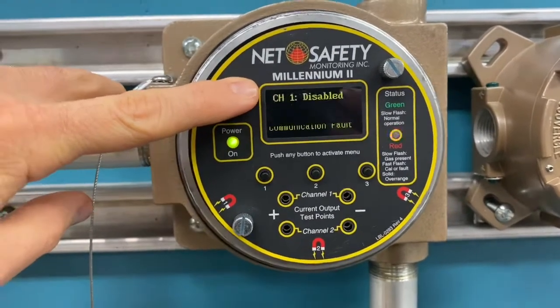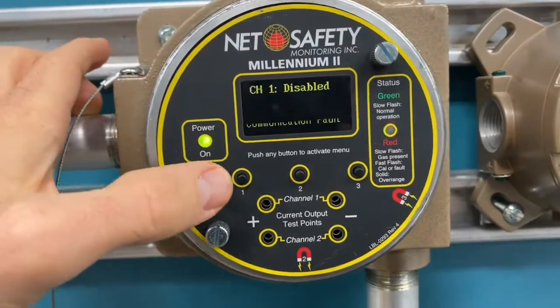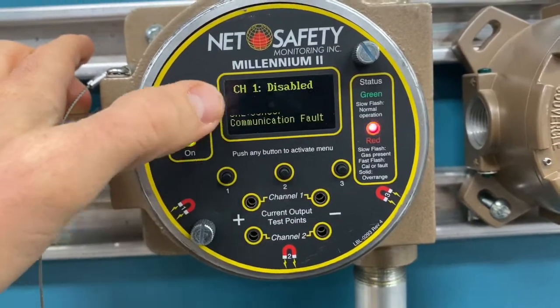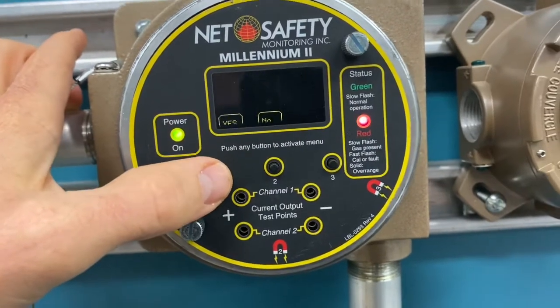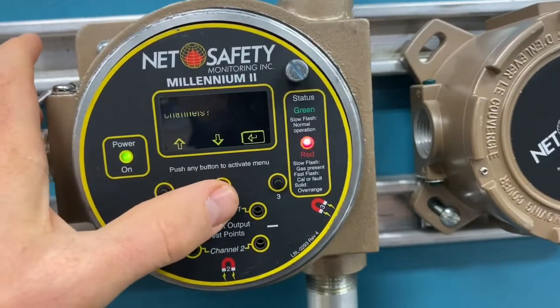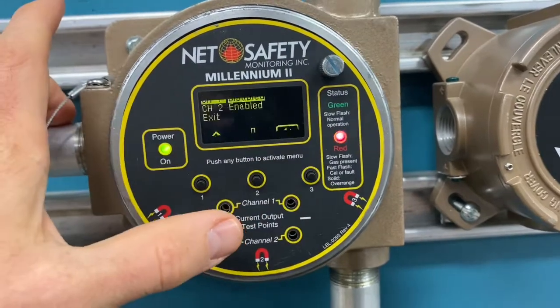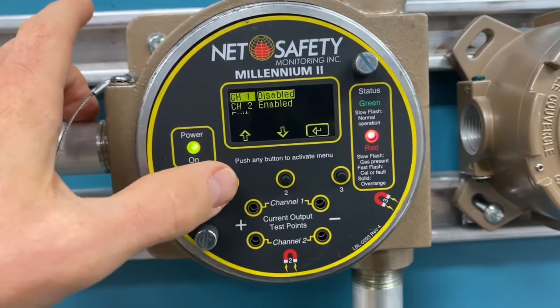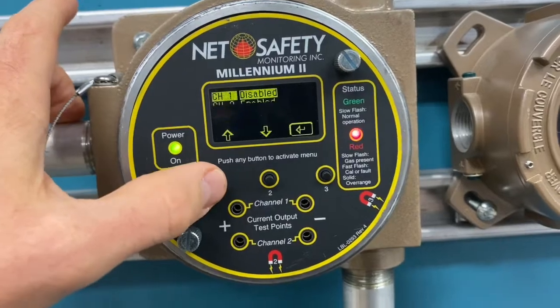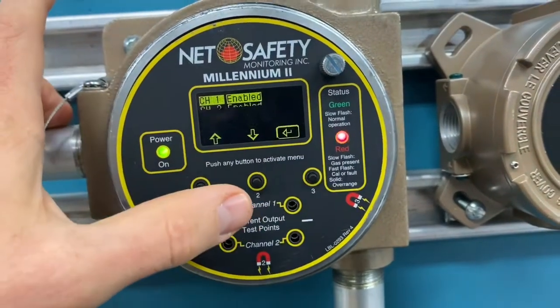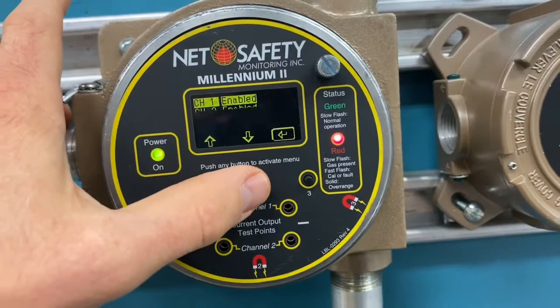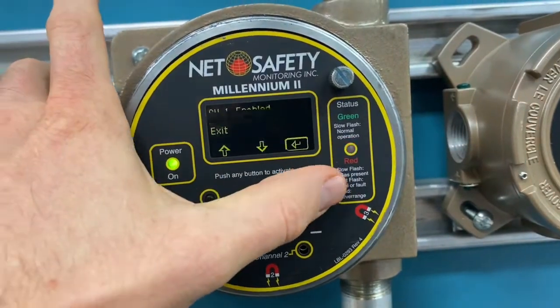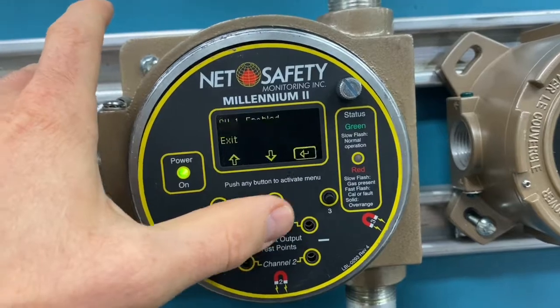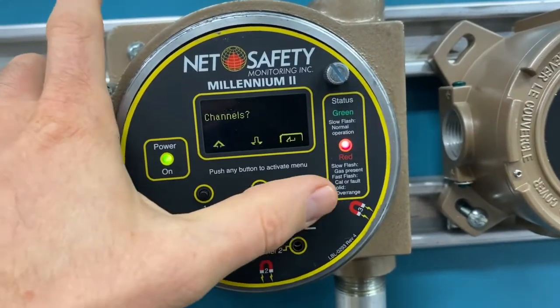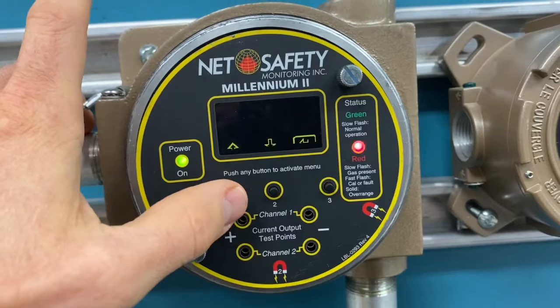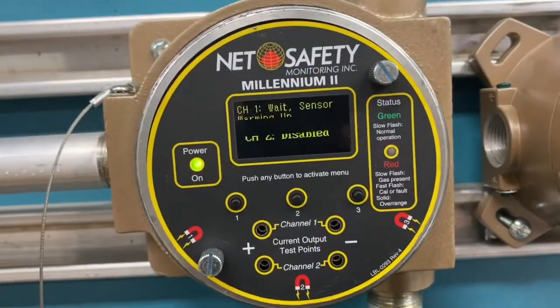So what we're going to do is make that change here. We need to disable this sensor because we're not using it anymore, and enable this one. So I'm going to bring up the main menu here, and I'm going to navigate down to enable, disable channels, and we want to enable channel 1. So press enter, and channel 1's enabled, and then we'll scroll down and we want to disable channel 2, and then we'll exit and go back and exit, and now you can see that our sensor is warming up.